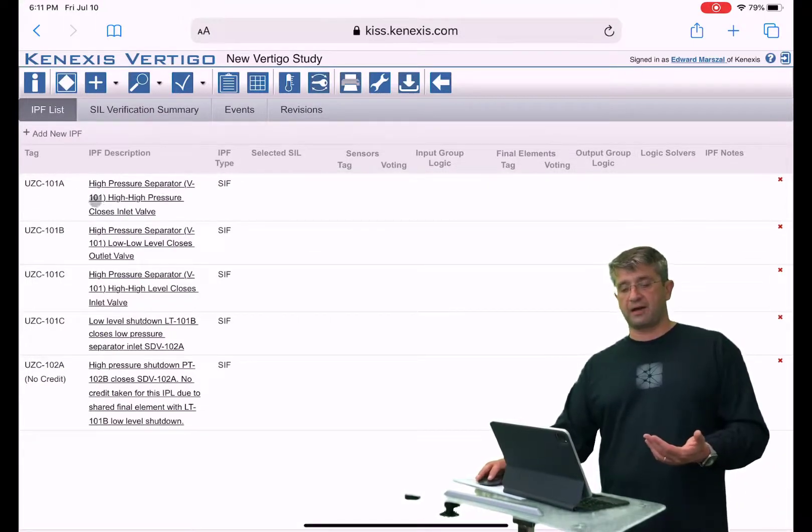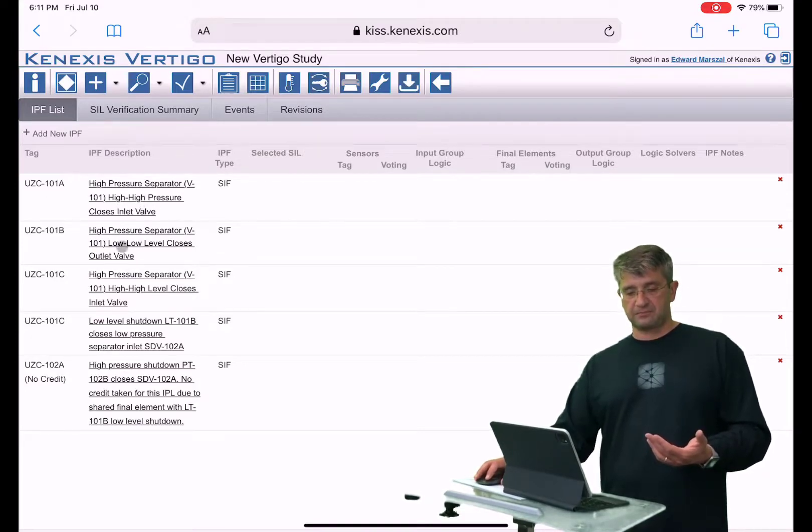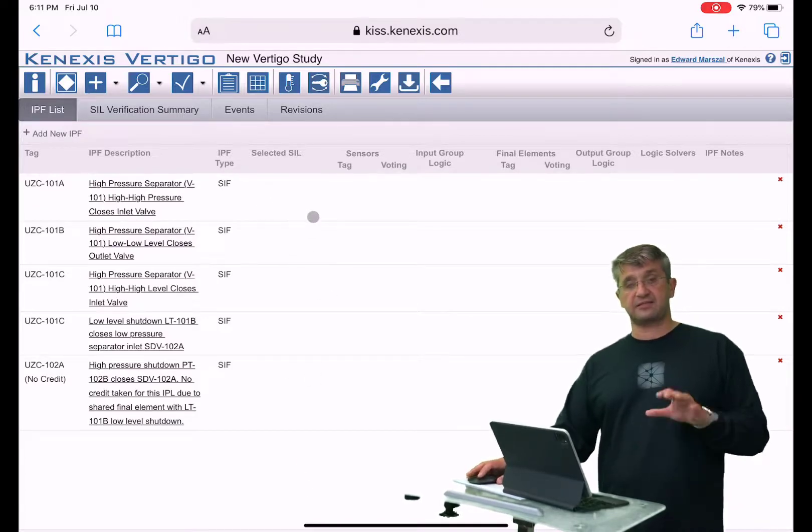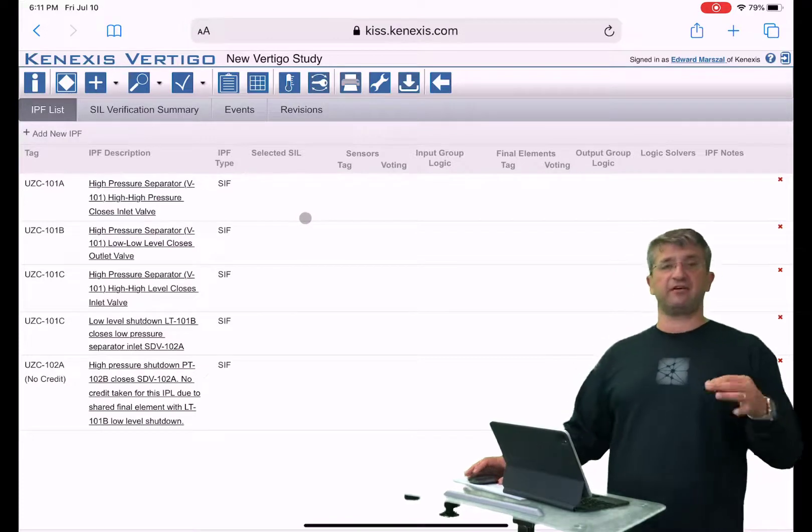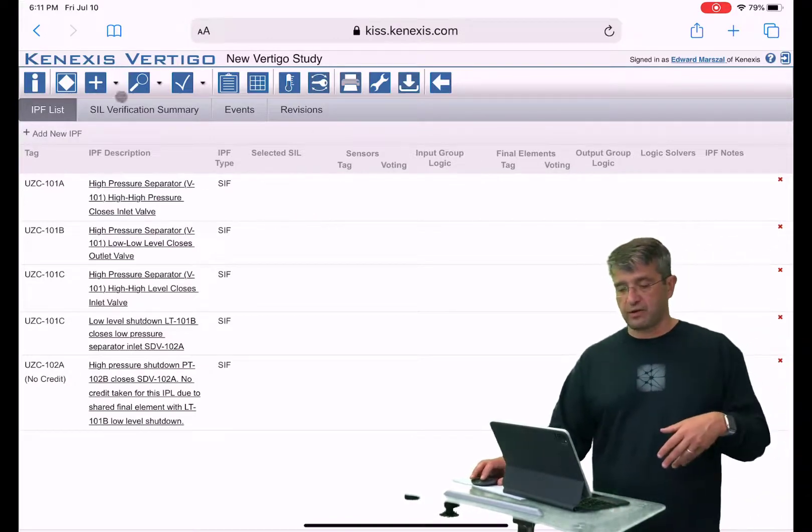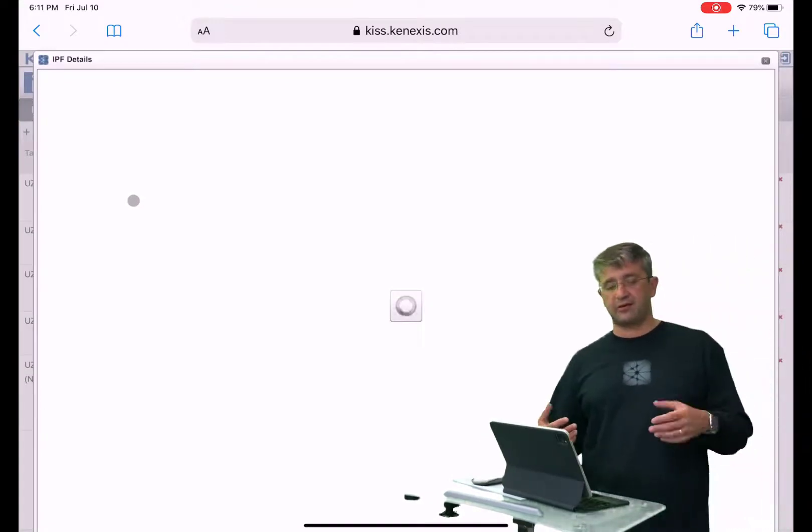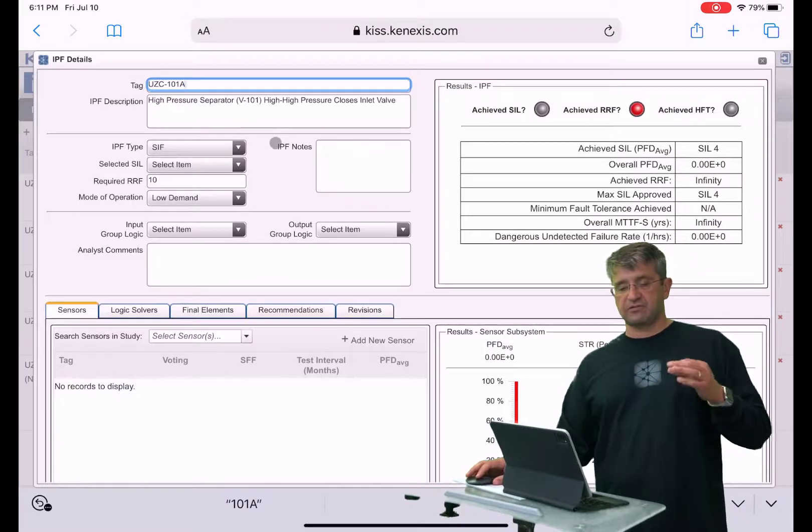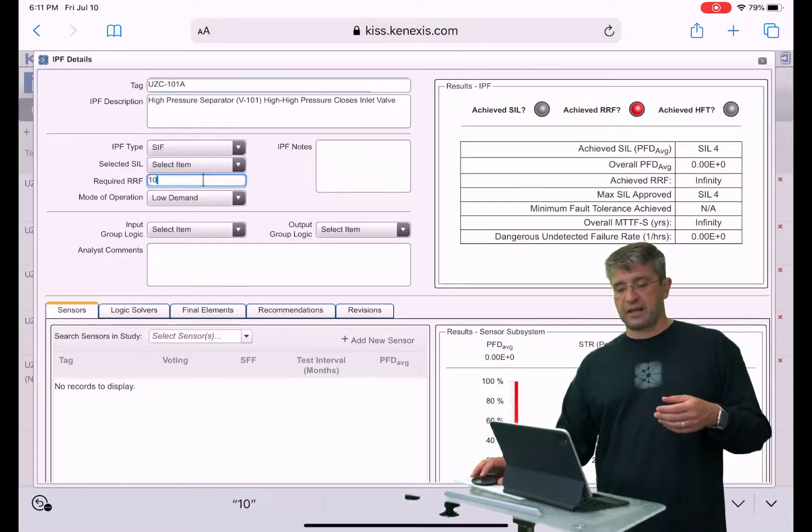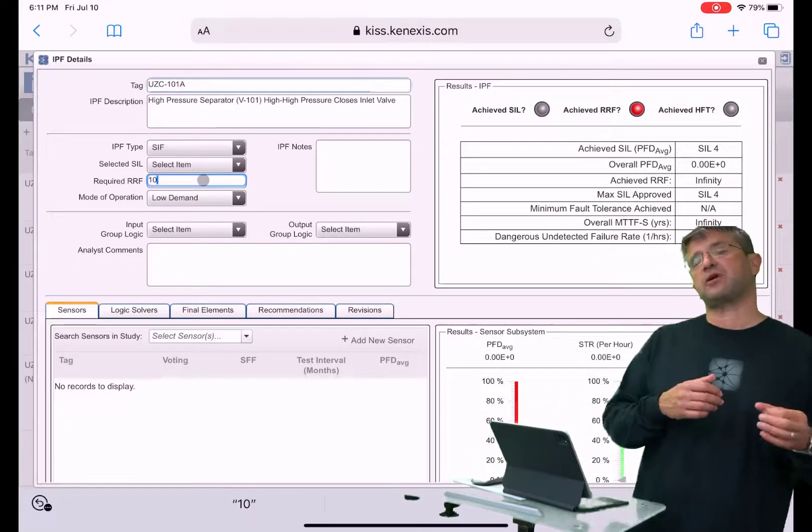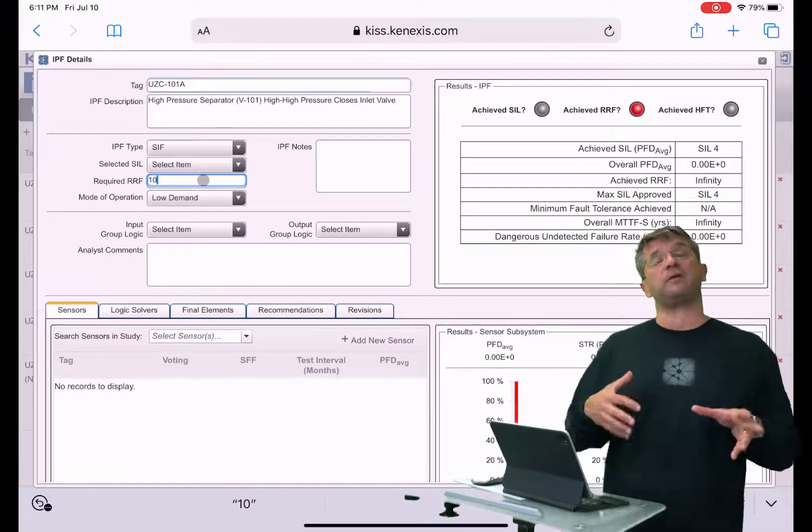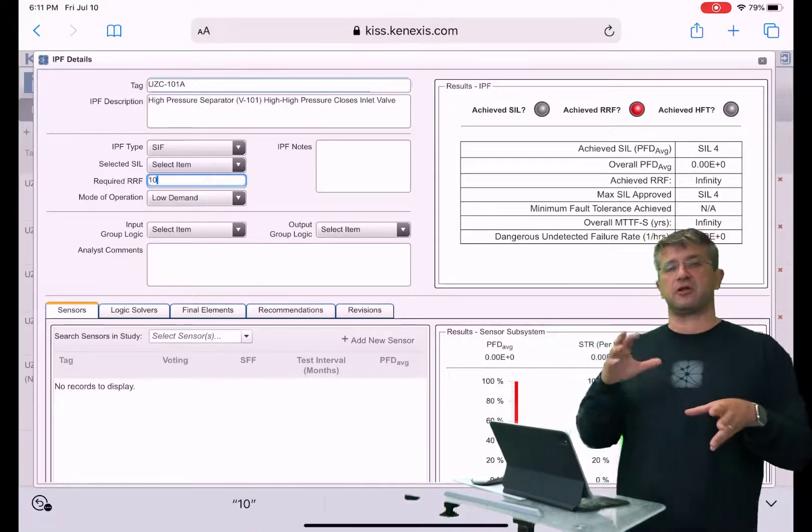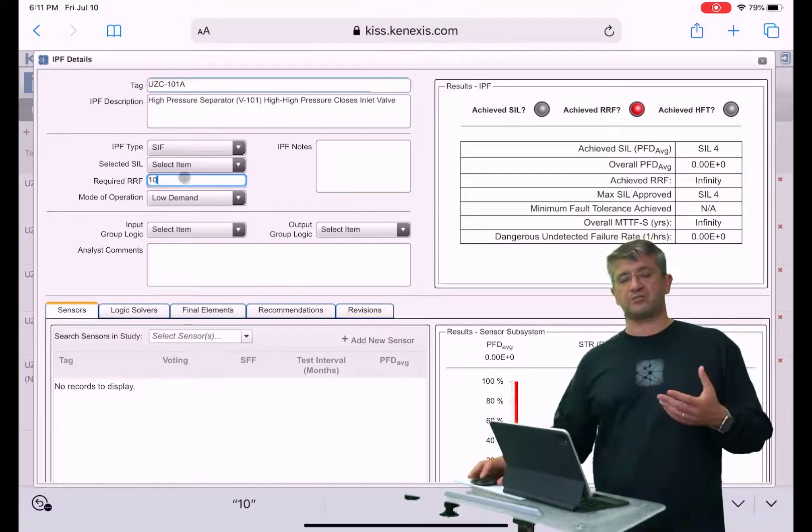Here are my safety instrumented functions with the tag numbers and descriptions. Now I didn't have a selected SIL listed in the IPL table—if I would have had them they would have carried over. So if I want to then click and look at these in more detail in the IPF details page, you'll see that even though the SIL didn't carry over because it wasn't listed, I was able to carry that required risk reduction factor, which is essentially one over the PFD that was assigned to that safety instrumented function during the explicit LOPA process.